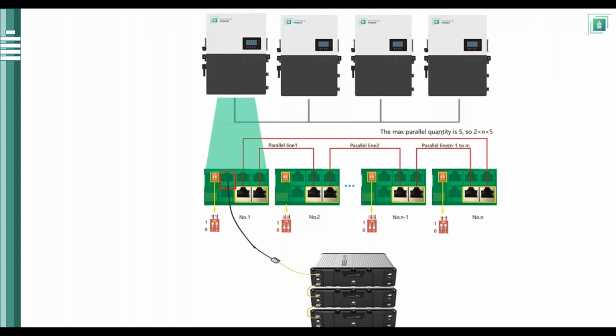So if you're paralleling multiple inverters, then you would go on the inverter communication board, and to communicate them you would run an inverter cable from the first communication board up to the second board of the inverter on these paralleling ports. The same goes for the second to the third and the third to the fourth. And then to secure the communication with better quality, we also connect a communication cable that goes from the first board all the way to your last board. Now we do provide some Ethernet jacks or Ethernet ports. So all you would have to provide is communication cable, and then you can crimp it on site and make that connection.